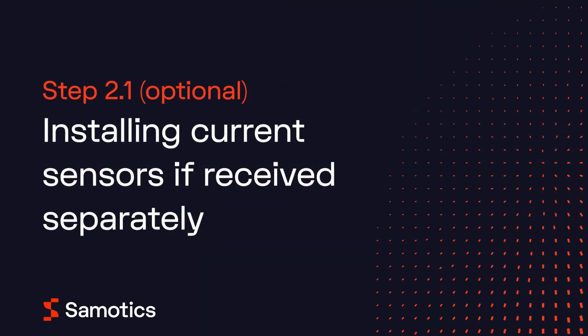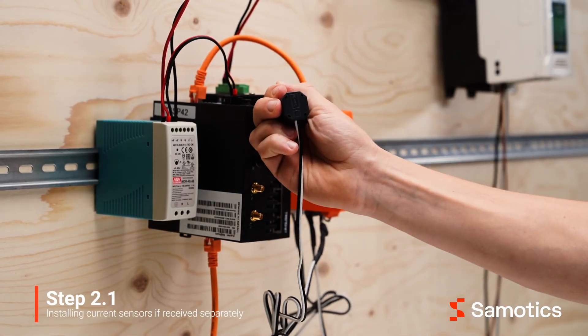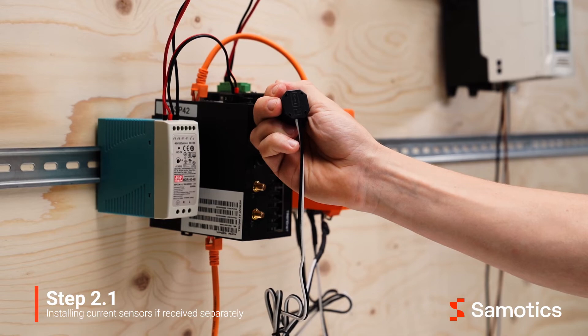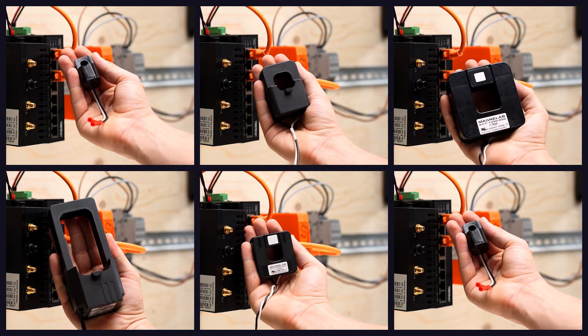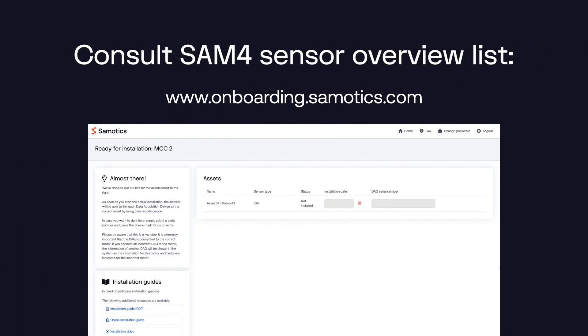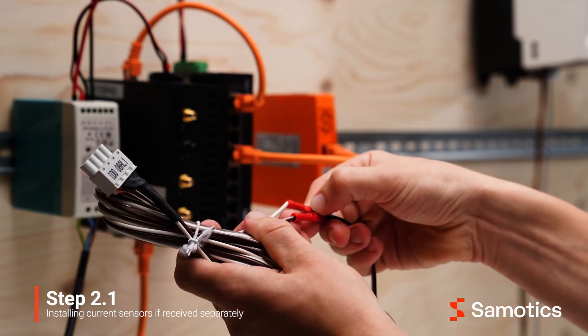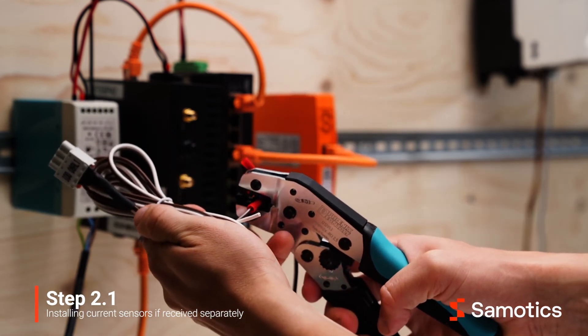The next section explains how to install the current sensors if you receive them separately. The sensor type depends on the amperage of the motor and the diameter of the phase wires. Make sure that you select the right sensors for each motor from the hardware you've received. Consult your SAM4 sensor overview list to double check. First, connect the current clamp to the cable set, making sure that the cable set matches the clamp type.